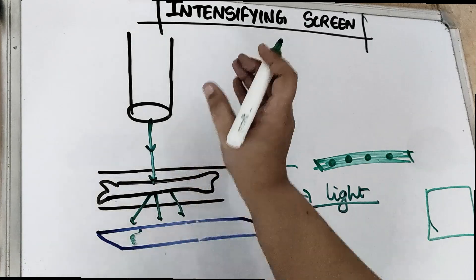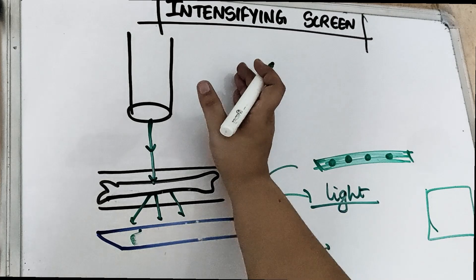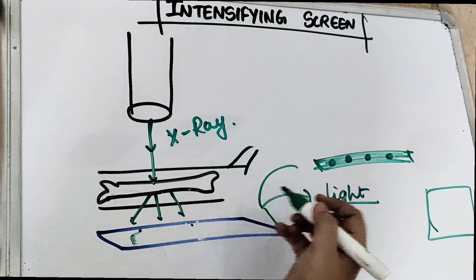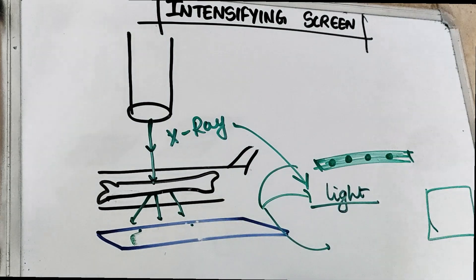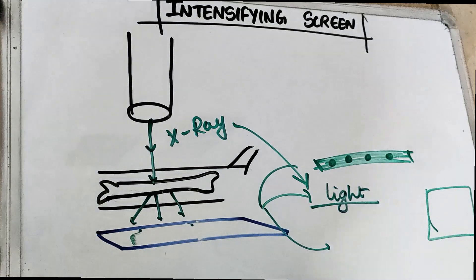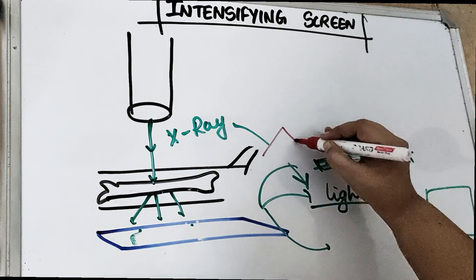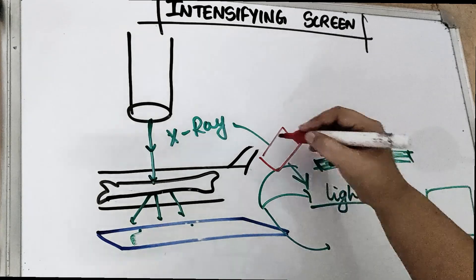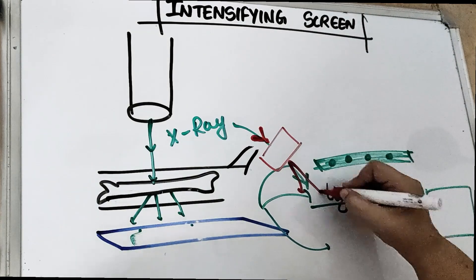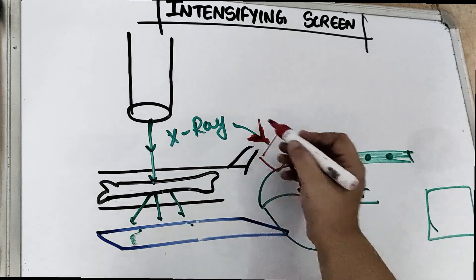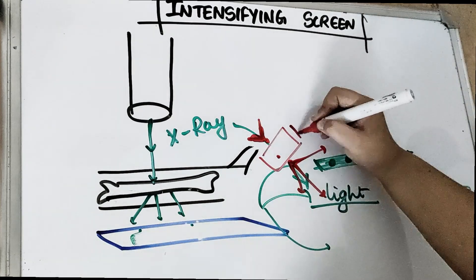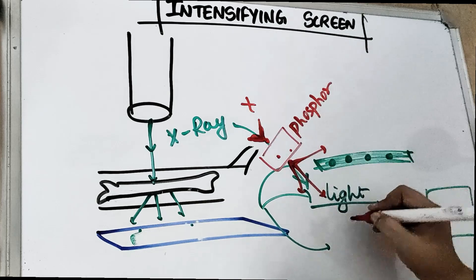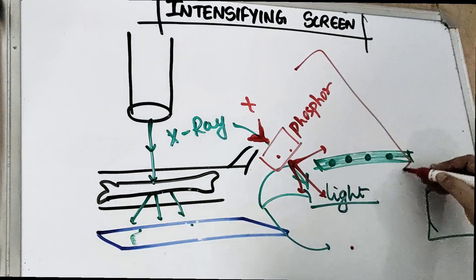Today's video we are going to talk about the intensifying screen — where we use it while converting x-ray radiation, the photon radiation, into light radiation. We have got a substance called phosphor. When we pass this x-ray radiation through phosphor, this substance converts the x-ray radiation into light radiation. This procedure we call luminescence.